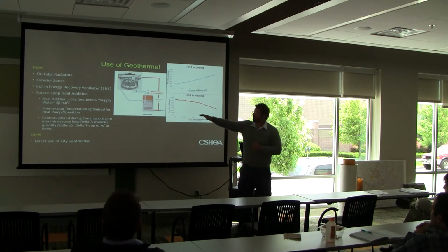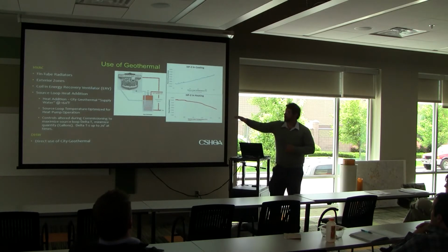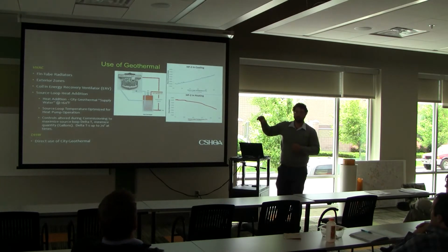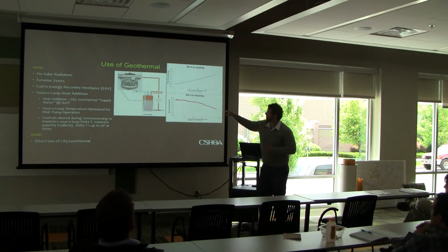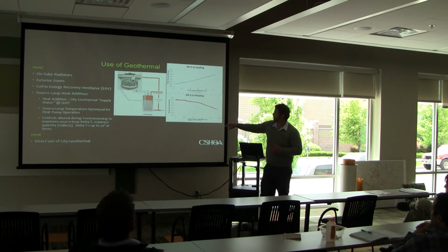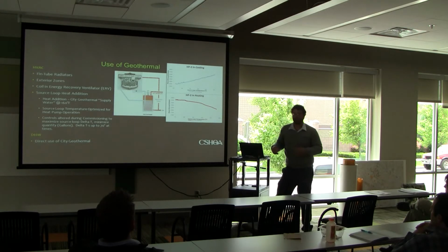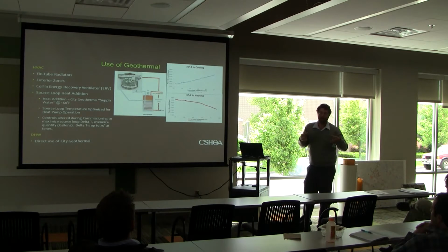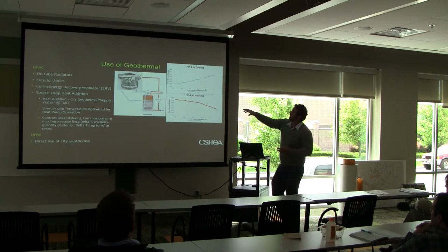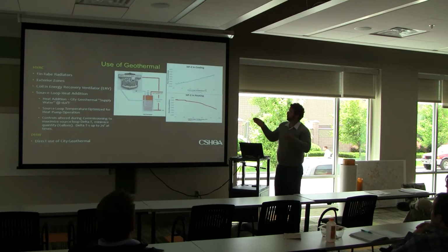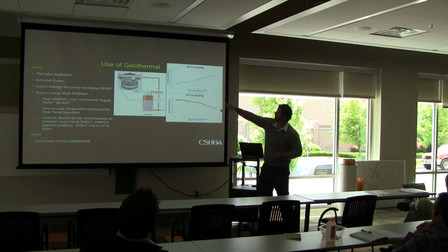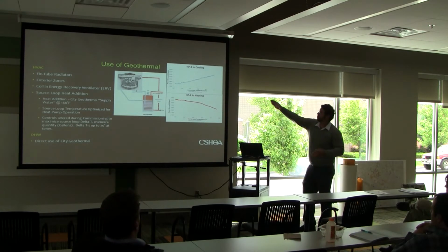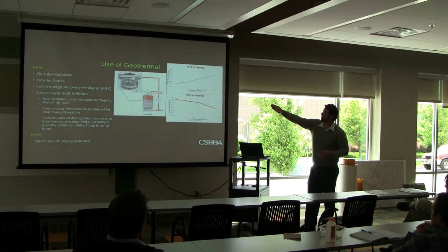The source loop temperature optimized for heat pump operation. Okay, so that's what I was alluding to in the previous slides. These are graphs of wattage of the heat pumps themselves versus source loop temperature, which would have a direct impact on how we use geothermal or the cooling tower up on the roof. As you can see, even the water-to-air heat pumps, even though they're incredibly efficient on both ends of the spectrum, can still get even more efficient depending on where you keep the source loop temperature.